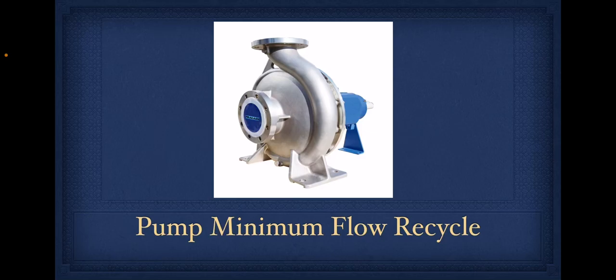All centrifugal pumps have a minimum flow below which the operation becomes unstable because of internal recycling. If the centrifugal pump is required to operate below the required minimum flow, it is necessary to provide a recycle line to ensure that the pump flow is always above it.